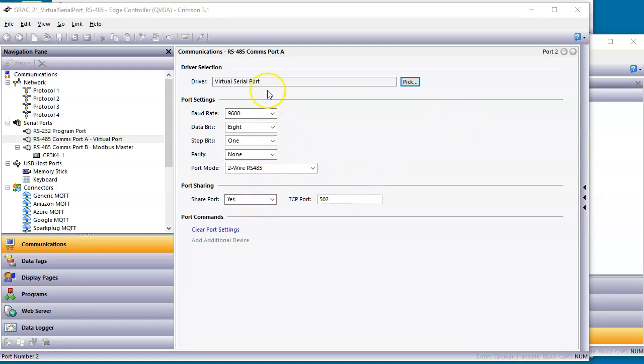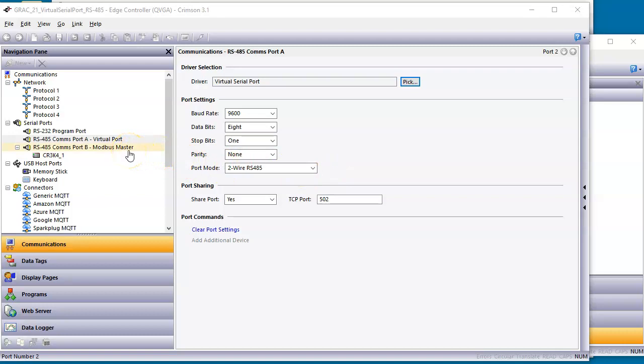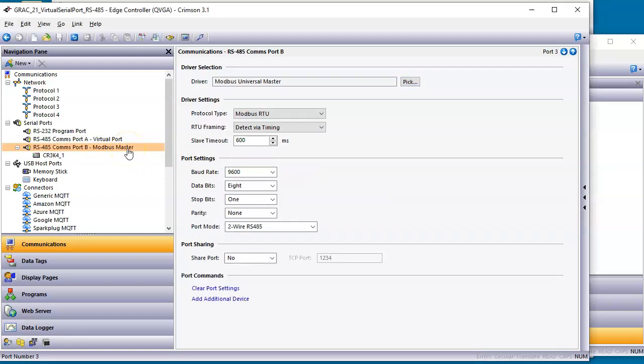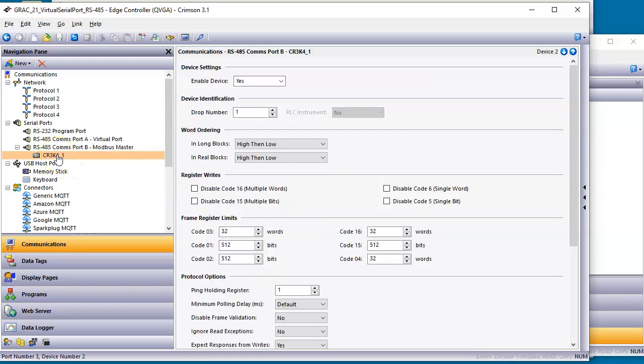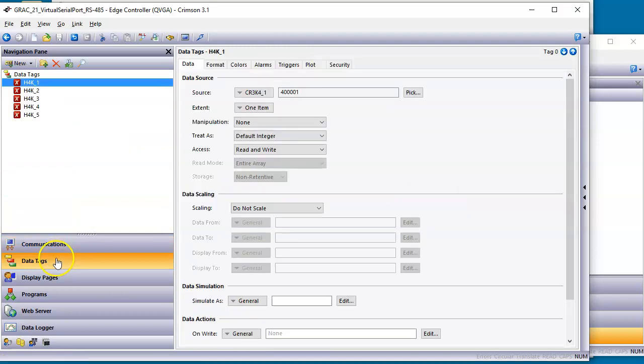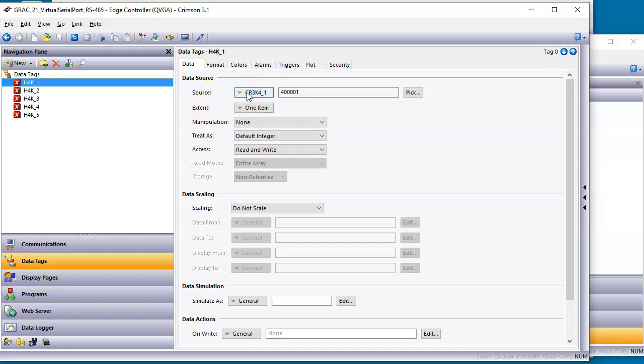The only other difference here I did with this virtual serial port is down here where I say share port. I said yes to this and I'm using port 502, the same Modbus TCP port. The other thing I've done here, I always like to check to see if the 485 port works. The GRAC unit happens to have two RS-485 ports on it. So I've set up another one here acting as a Modbus master. I've got here the device that it's polling. And if I go over here to data tags, I have five tags that are mapped to that unit. That way I can actually test that communications and I'll demonstrate that in a second.